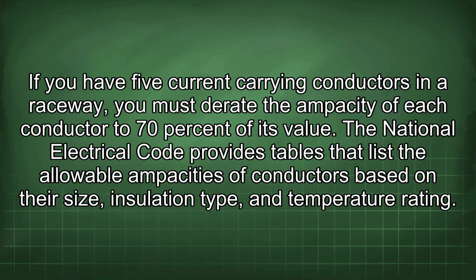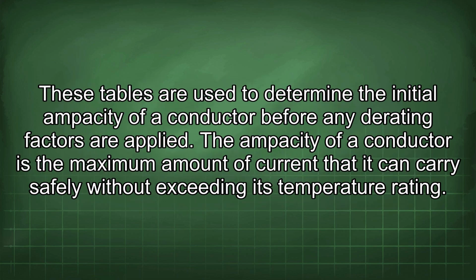If you have 5 current carrying conductors in a raceway, you must derate the ampacity of each conductor to 70% of its value. The National Electrical Code provides tables that list the allowable ampacities of conductors based on their size, insulation type, and temperature rating. These tables are used to determine the initial ampacity of a conductor before any derating factors are applied.